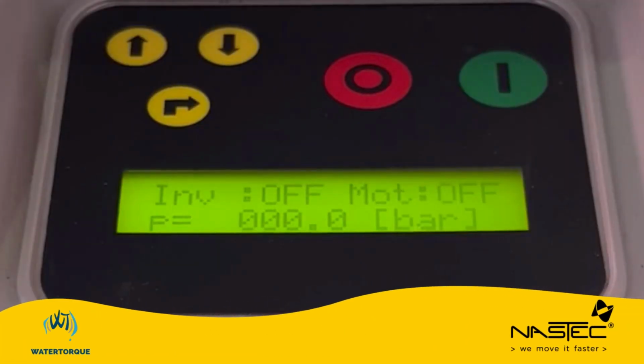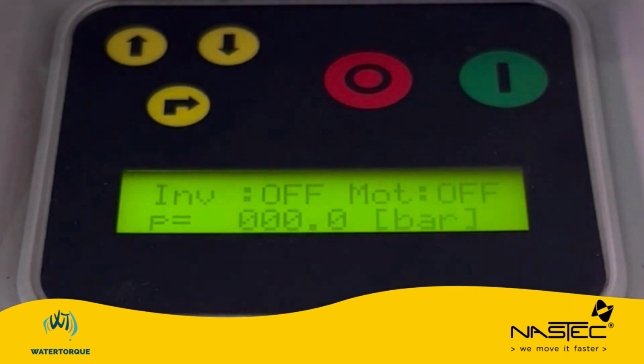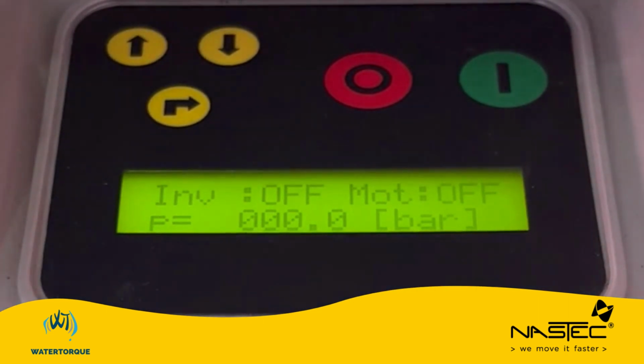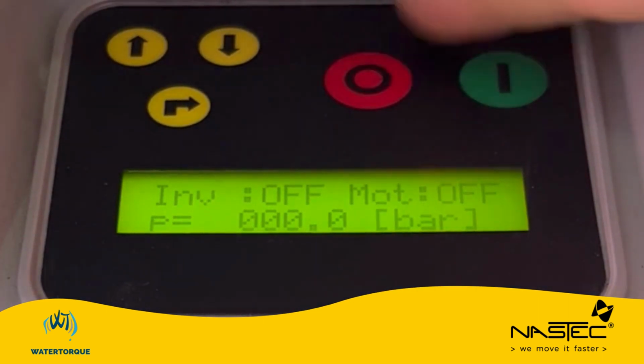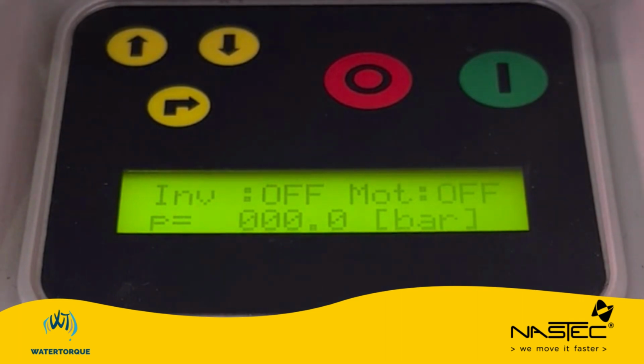Today we will be programming a Nastec 4HS0504 on constant value mode. First things first, what we need to ensure is we have INV off and MOT off. The way that we do that is we hit the red button twice if it's not already in the off position, and that will turn the inverter and the motor off.